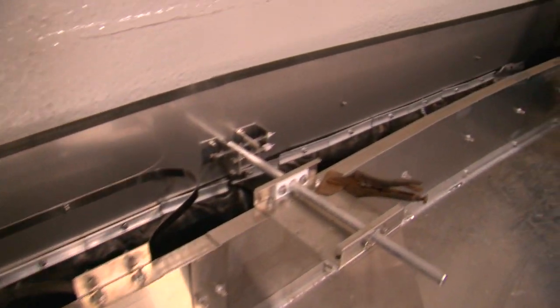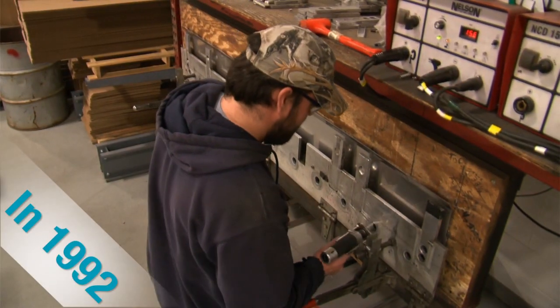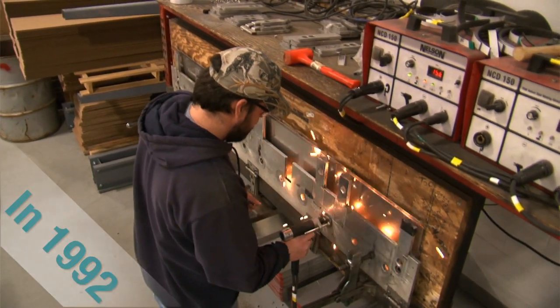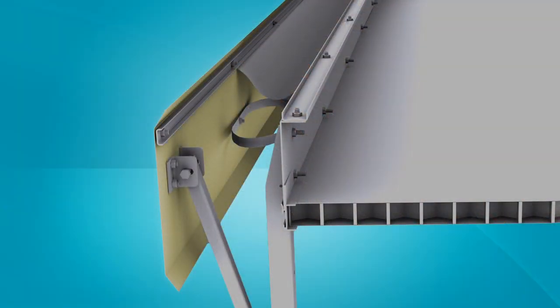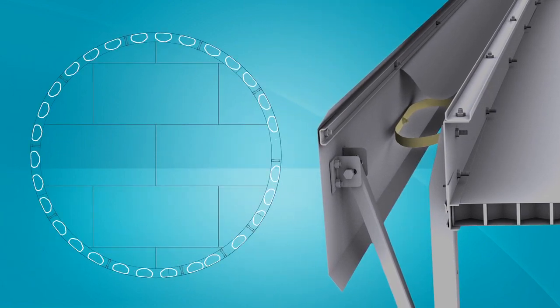This high amount of buoyancy is able to support our double stainless steel shoe seal, the premier seal in the industry. In 1992, Allentech introduced the only shoe seal specifically designed for aluminum internal floating roofs. Our stainless steel mechanical shoe with its Teflon vapor barrier offers a 20-plus year design life and excellent overall performance because of its resistance to most chemical products and ability to stand up to extreme temperature variations. Our system of tightly spaced hoop springs exerts a nearly constant force against the tank shell to maintain the seal.